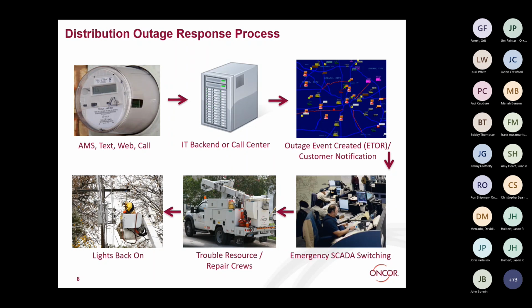By operating switches. If I have the switches SCADA enabled, I do it remotely. If not, I have my people in the field go out there, opening and closing switches to isolate that fault. Once I have it isolated and located between which switch or which protective device it is, I restore power to the surrounding customers by bringing in power from a neighboring feeder or using tie points to neighboring feeders. That's the typical restoration point.